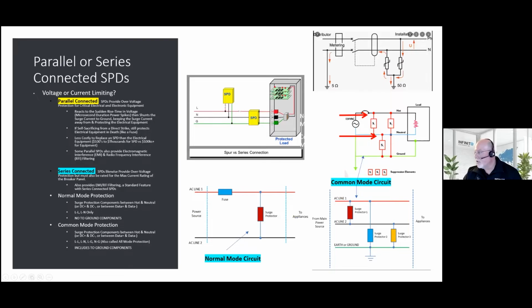And then schematically, you see the components here. These are the surge components. And I like this slide too, because the surge arrestor can be a common mode protector or a normal mode protector. And what's the difference? With a common mode, you have components that are between line to neutral and neutral to ground and line to ground. That's a common mode protector. If you don't have components that go to ground but are literally just between line and neutral, and that's all, that's a normal mode protector.